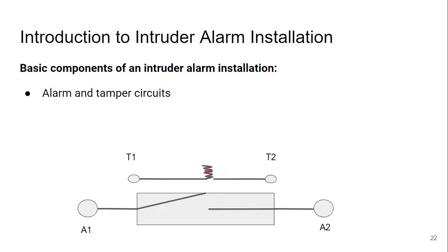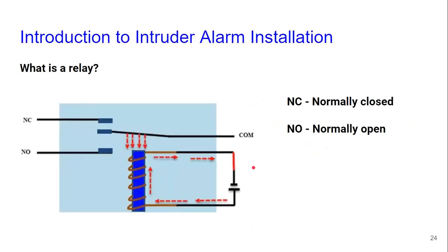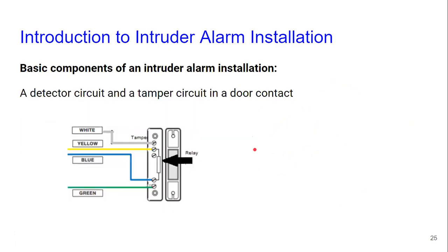You have two circuits in one alarm circuit: the alarm circuit and the tamper circuit. Normally closed means the circuit is closed; normally open means it's open. With alarm systems, 95% use normally closed circuit because if it's normally open it's quite difficult to monitor tampering — the circuit is already open. So most of the time you'll come across normally closed circuits.